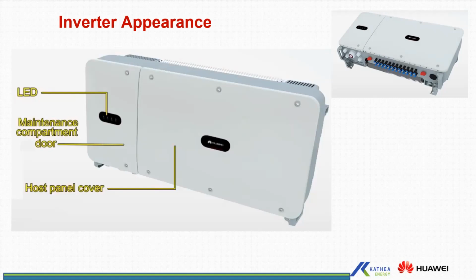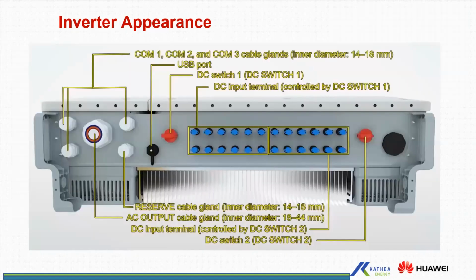So this is how it looks. And then underneath the inverter, you have your MPPTs, which is 6 of them, and this is the 56 KTL. And then you have two strings per MPPT, so you have actually 12 strings. You have 2 DC switches, which are red on the diagram. DC switch 1 controls the first 3 MPPTs, and DC switch 2 controls the other set of MPPTs. And then underneath there are glands where you need to put through your cables. The bigger one is for the AC cable output, and the smaller ones are for comms cables, mainly the RS485 line.